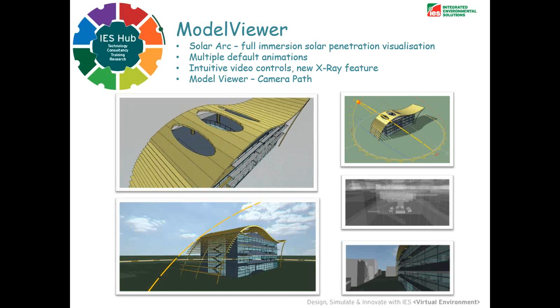We actually have a system with a very large retail chain in the United States, where they're constantly monitoring their building. They have a weather station on top of each building. They run a simulation, and at the same time read the data coming from their building systems, and compare them. So if for some reason the cooling loads are peaking on the actual building but not on the simulation, they know something is wrong and can send out a team to fix it. Something like a damper stuck open or a fan not cycling will cost you thousands and thousands per year. It's something silly, but sending someone to look at it and fix it saves money and makes it perform as you want. That's the key with that.